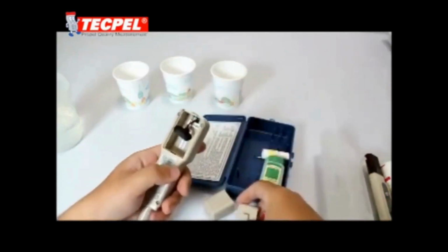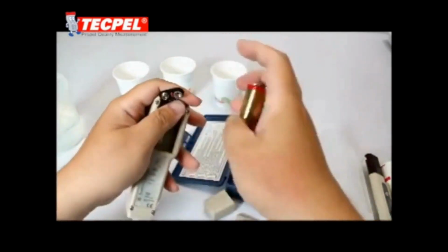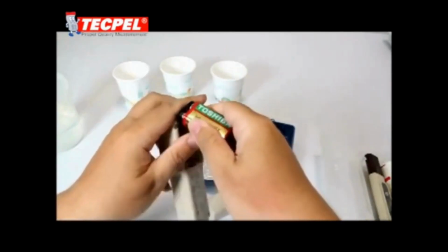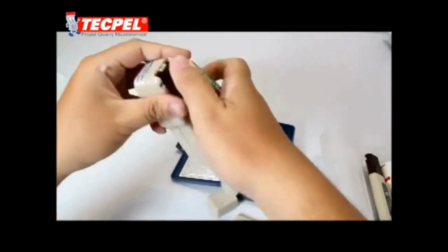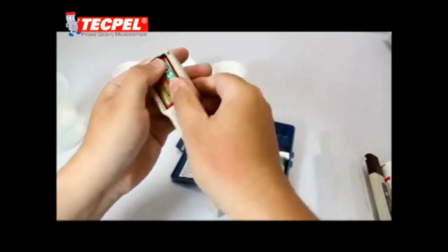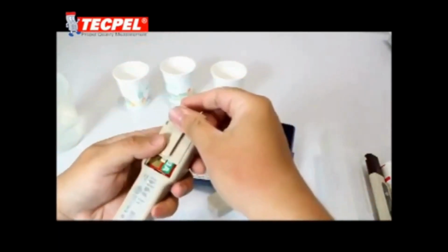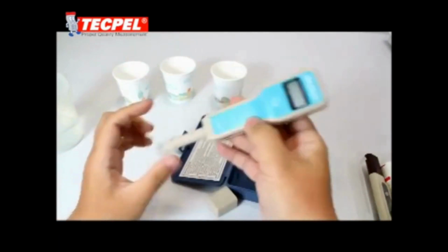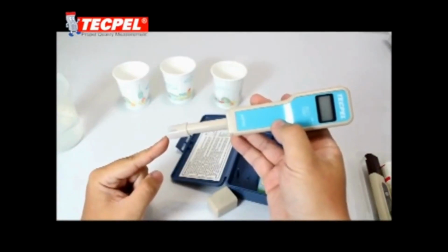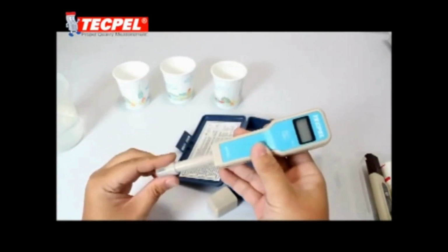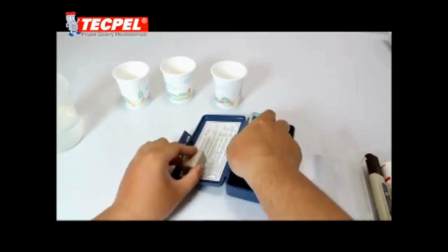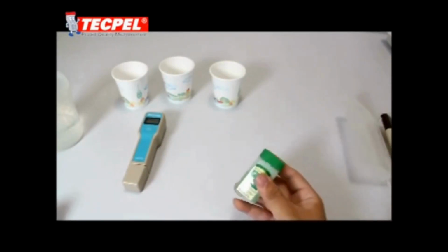The TECPEL pH-703 is a portable pH meter with an all-in-one design. The sensor and the main body are integrated together, meaning they cannot be removed or replaced. This structure ensures a stable, durable, and easy-to-use measuring tool. Before the first use, the included battery must be installed, and the protective cap covering the sensor must be removed. Once these steps are completed, the pH meter is ready for setup and calibration.